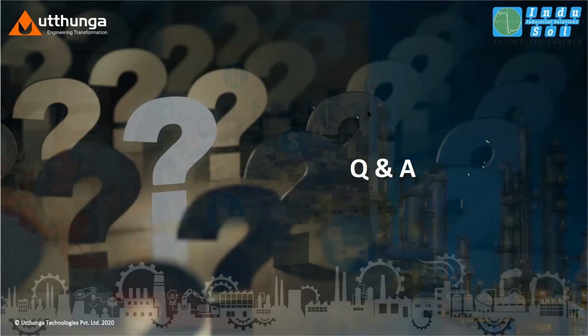The next question is, if you want to check the instrument to PC communication, which software should you use? For the PBQ1, we have dedicated software, PBQ Suite. You have to install it. It is free software along with the product. You install it on your system and connect through the USB port to our PBQ1, and the PBQ1 can be connected to any PG port. Profibus connectors have a female port. Any female port you can connect to and get the complete information.